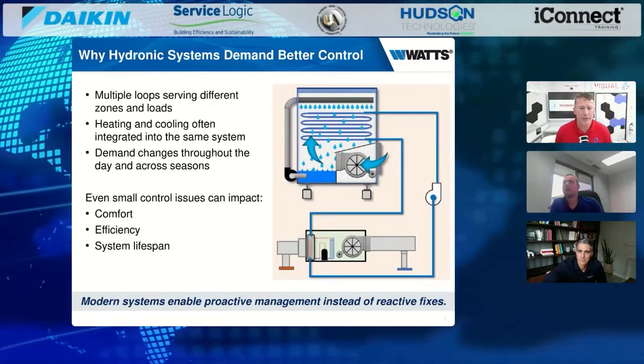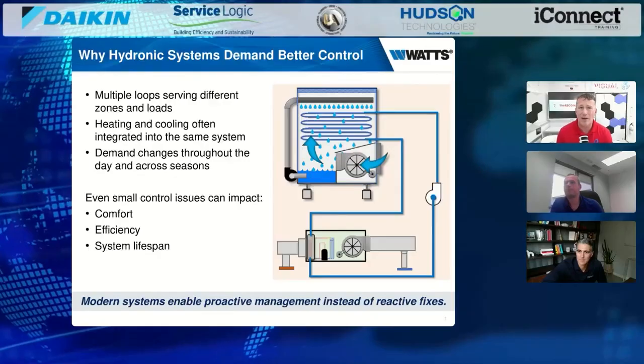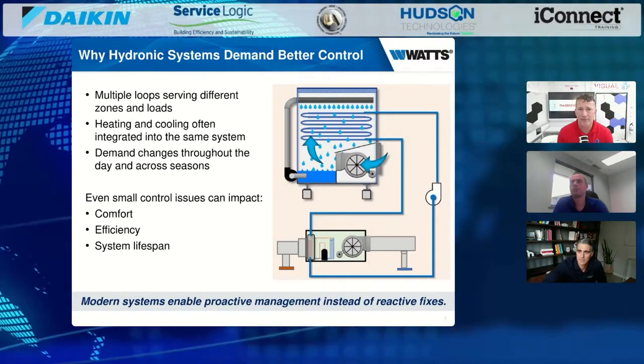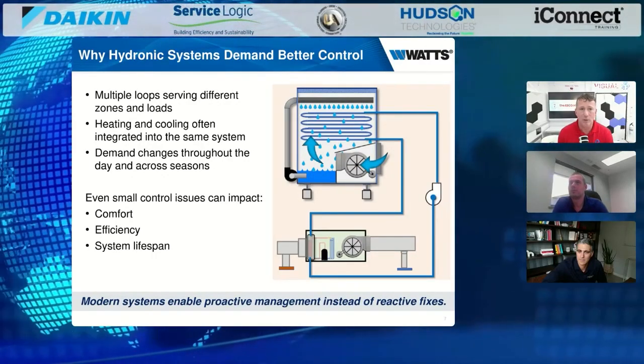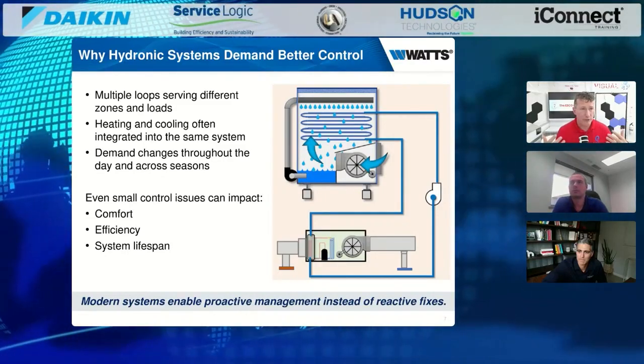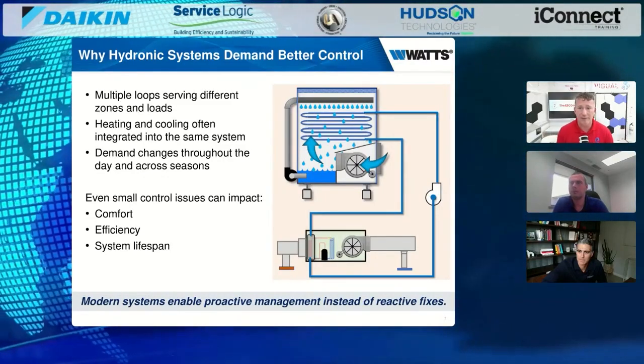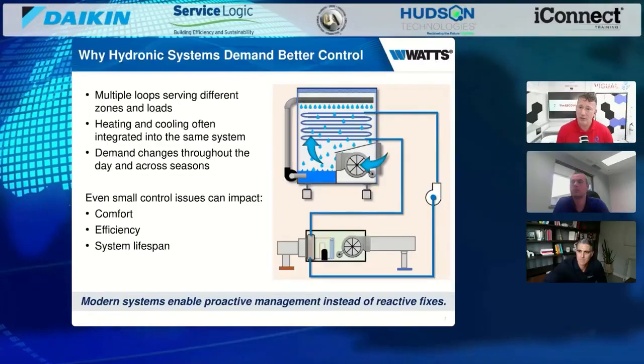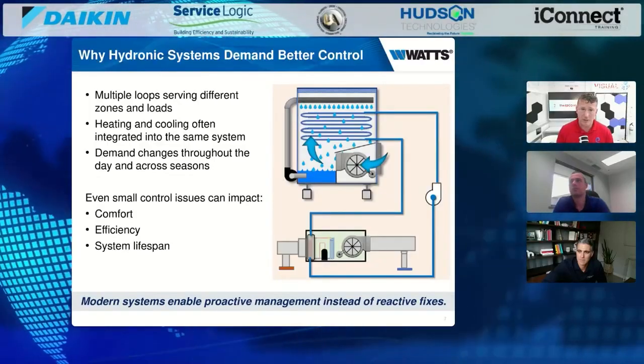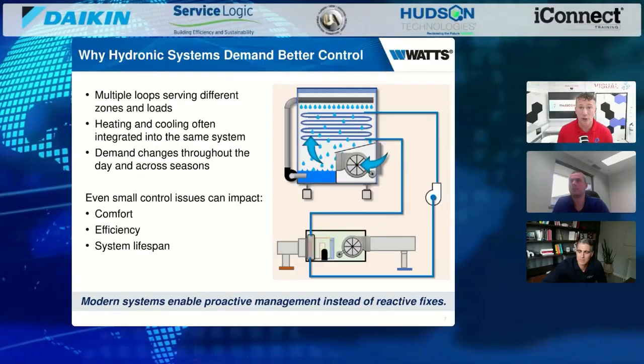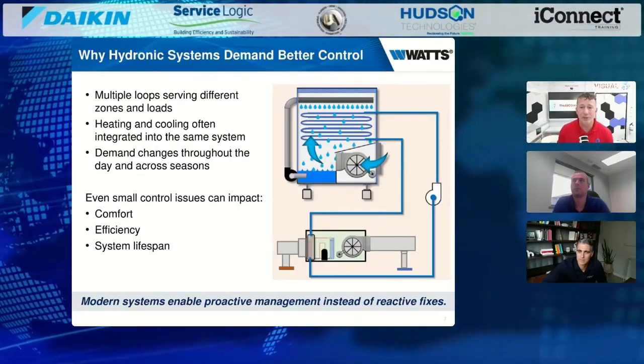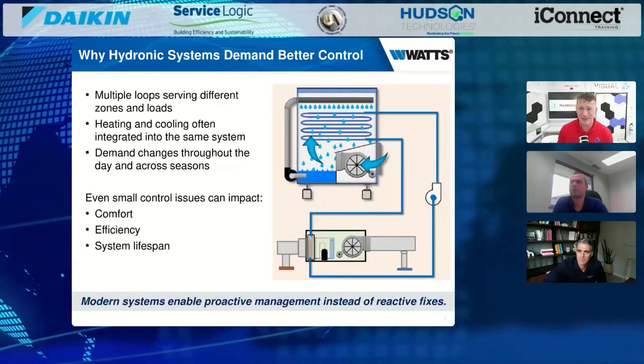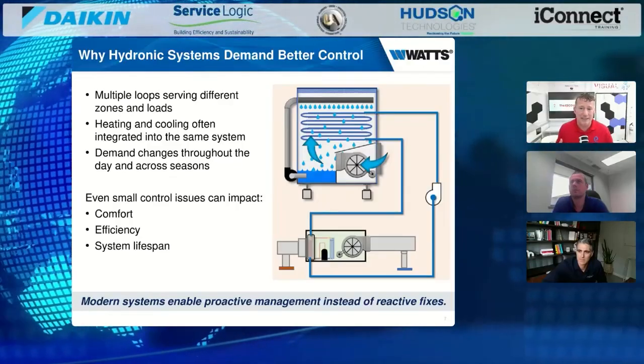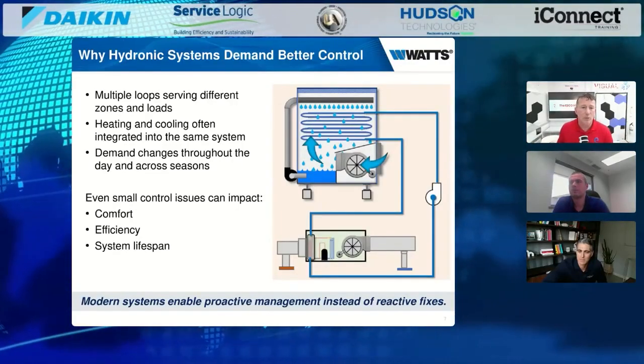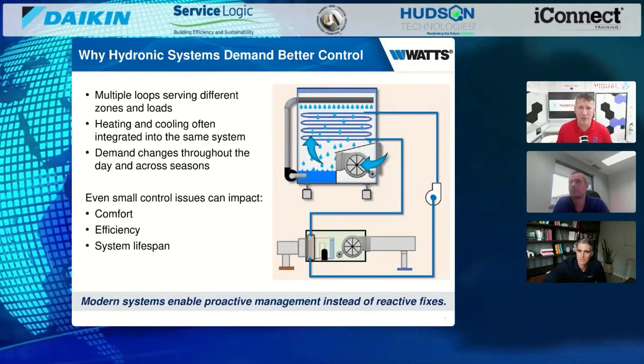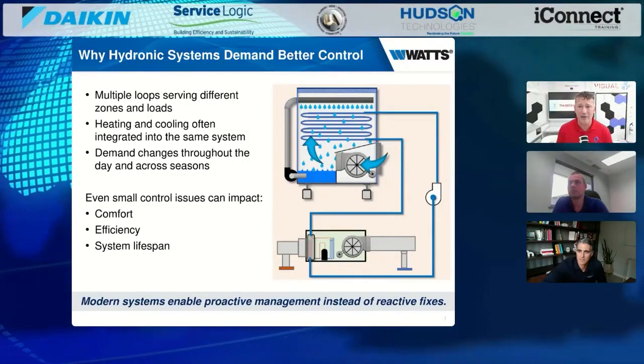A lot of engineers are really struggling right now with how to design multifamily buildings going forward, looking at whether to use heat recovery VRV/VRF or hydronic. Because our VRV/VRF systems are really going to struggle. We're not going to have good solutions for CO2 or A2L VRV/VRF systems because of the amount of refrigerant that would be inside the building. So when we look at our solution for managing temperature, especially in heat recovery style scenarios, hydronic is perfect.